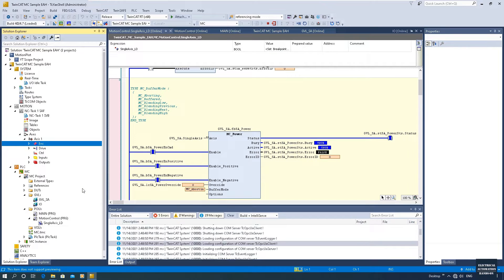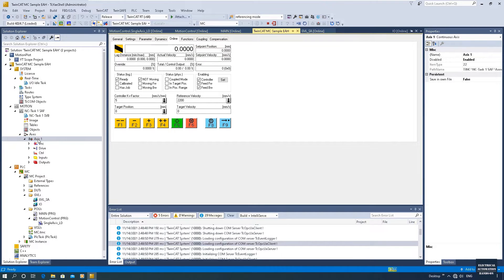Take this simple program as an example. In this project I have this axis 1 project. From this online panel we can see this axis is powered and enabled. The ready signal turned on means this axis is powered without any issue, and currently this axis is not moving — it's at a standstill status. The ready signal, moving signal, and error code are very important information for the drive and for the axis. So how can we read the error code and the status from our drive?